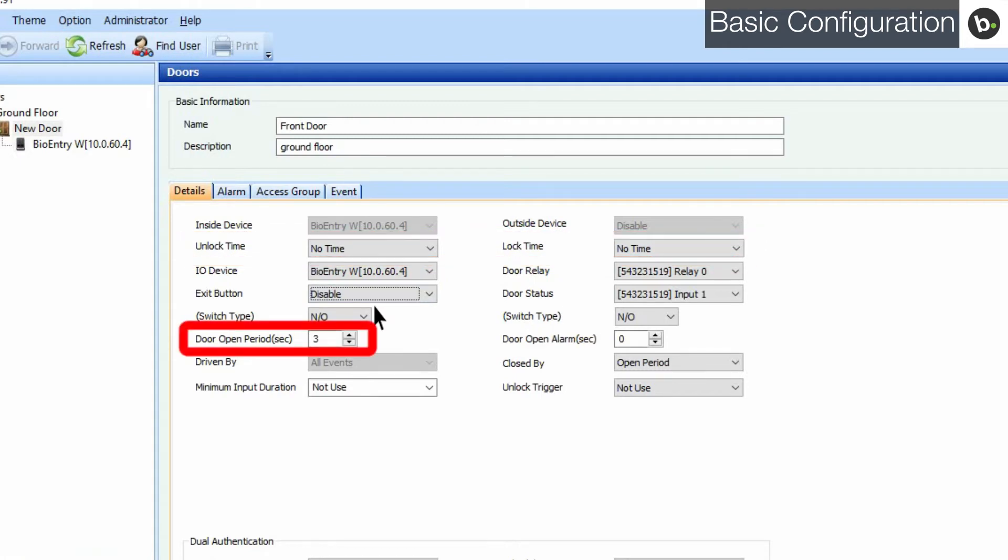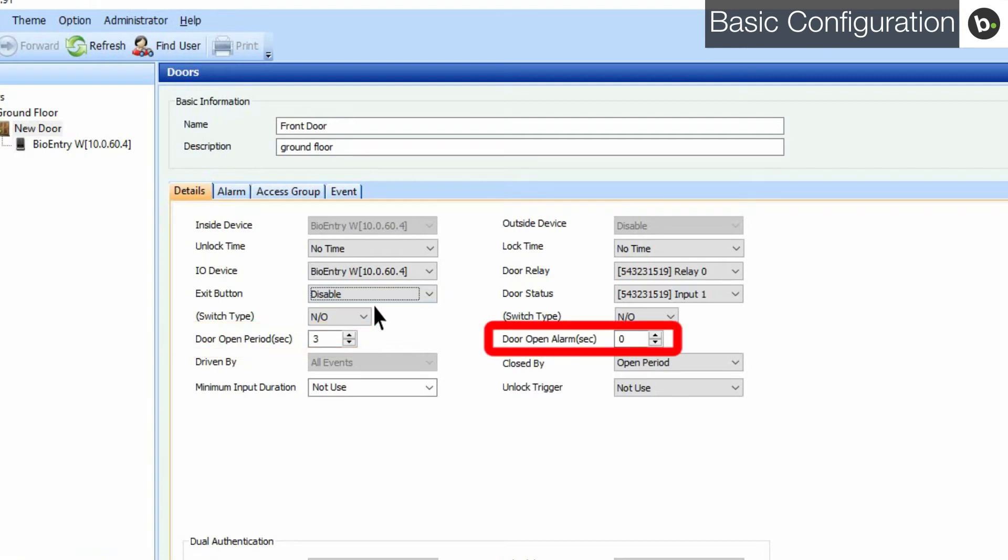The door open period is how long the door will stay unlocked after it is unlocked by a user, and the door open alarm is how much time will pass before an alarm goes off if the door is held open. If this value is set to zero, the alarm will never go off. Click apply to save your settings.